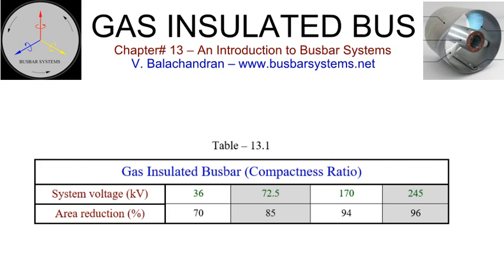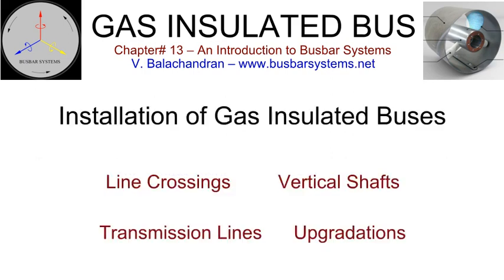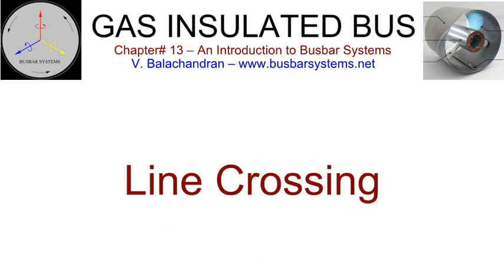The reliability of the support insulators, contamination of metallic particles, and susceptibility to very fast transient overvoltage, VFTO, generated by the operation of disconnector switches are inherent in the design of the gas-insulated bus and therefore need careful consideration. The requirement of GIBs has been mainly felt in the following locations: line crossings, vertical shafts, transmission line upgradations. Line crossing. There may be situations where due to line congestion, it may not be possible to lay an additional high-voltage connection to the existing switchyard or connect a new line for power evacuation during the expansion of a power plant, that results in the crossing of the existing lines.